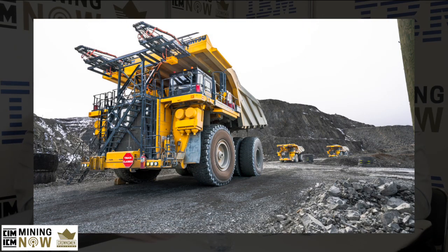And it's not a little bit of power — it's quite substantial. When we look at our 300-ton 930 class truck, that truck will consume four megawatts of power while it's under the trolley line at full load. These are very high power. You start looking at multiple trucks on the line and you end up with some pretty well-designed DC substations. On the incoming power side, you have your grid power or other power available. You bring that into basically an electrical house, that power is transformed from AC down to DC, and then that DC power is fed out onto what they call the catenary line.